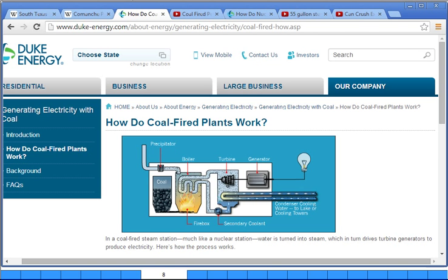Once it's passed through the steam turbine, it's low pressure. It's condensed in a condenser. It's usually cooled with other water, a different source of water, either going to a lake or a cooling tower. In Texas, we have a lot of lakes. We can build them. We use them. Some other places, they have cooling towers. They don't have the footprint. Land is too valuable to make a 7,000-acre lake like they have at South Texas Project. That's a lot of land, 7,000 acres for one lake to cool your power plant.